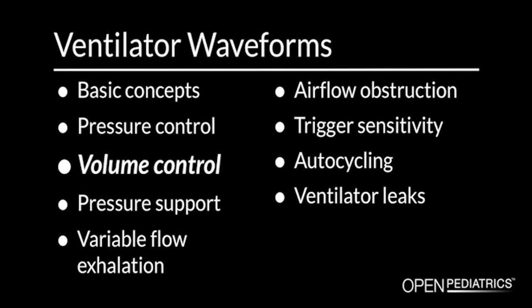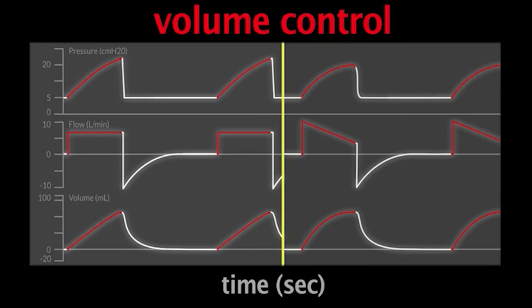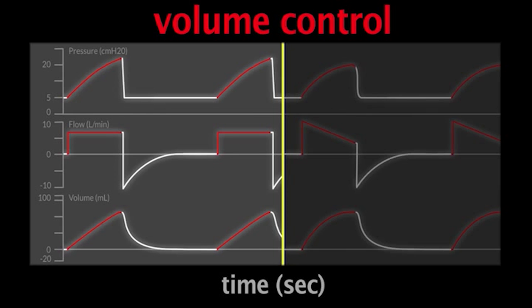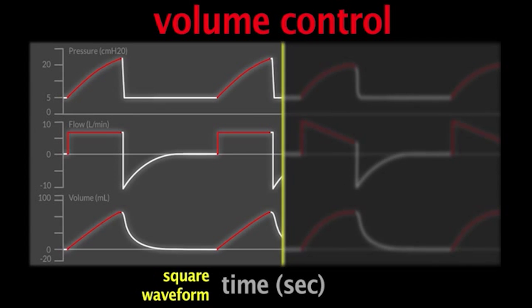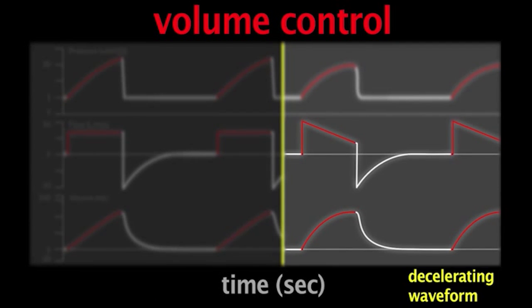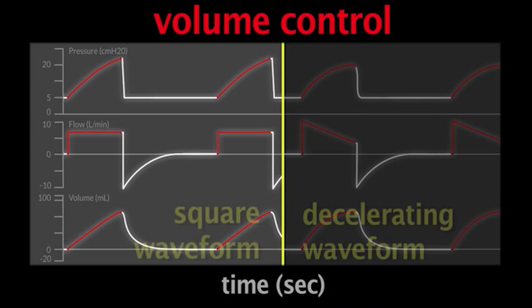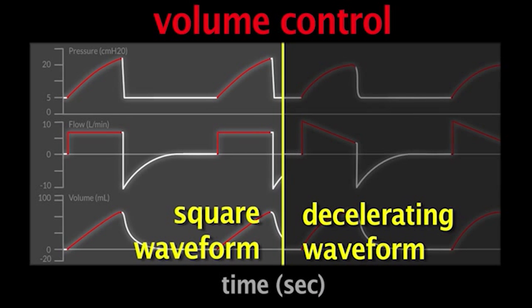Volume control. Now I'm going to talk about what a normal volume control waveform looks like. There are a couple of different ones — the most typical are represented here. On the left part of the waveform we have what we call a square waveform. Because we are controlling inspiratory flow in volume control, this has a very box-like structure. The other type is a decelerating wave flow pattern, which looks a bit more like pressure control but is still quite controlled. There is no real difference in benefit between these two; it depends on your ventilator and your preference.